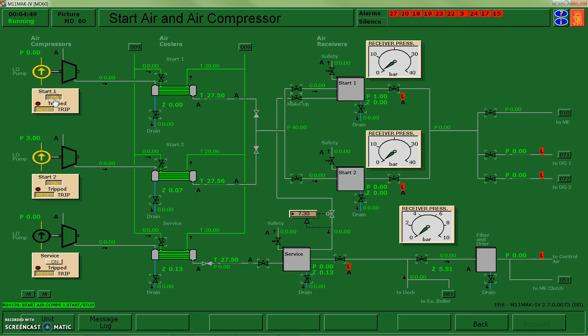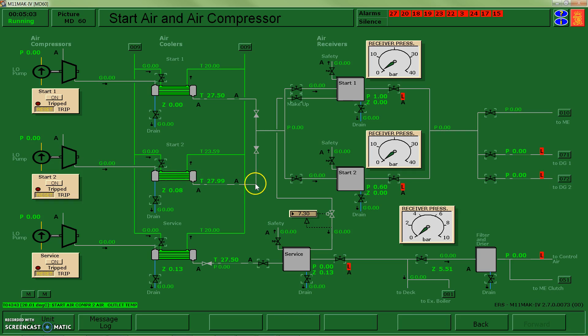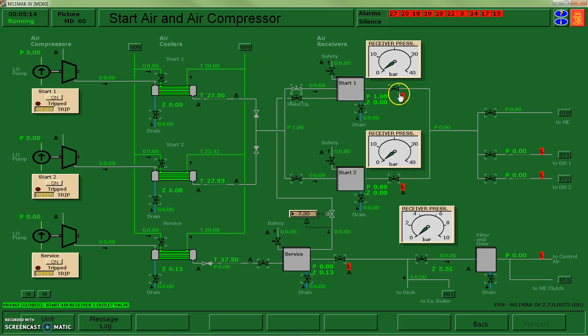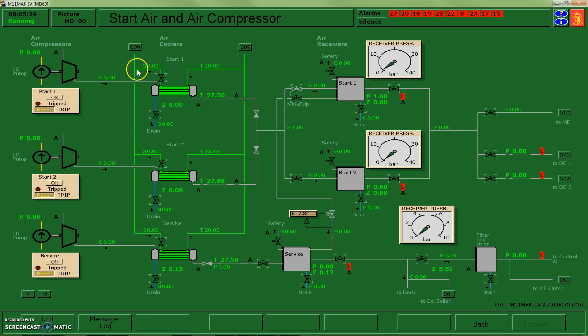I don't want to turn them on quite yet because I'm not quite ready for them to operate. First, I want to make sure I have a pathway. Following through my pathway, I want to add air into start air receiver 1, so I'll open up my valve there and make sure there are no other pathways open - drains are closed - so all the air can be directed into start air receiver number 1. I also need to get my cooling water system operating before I can run the air compressors. I need cooling water coming in, going past the cooler, and returning back to water system number 9.